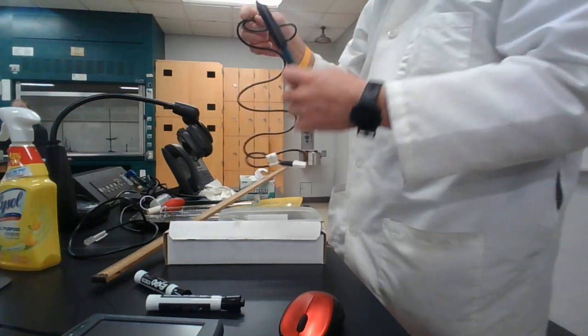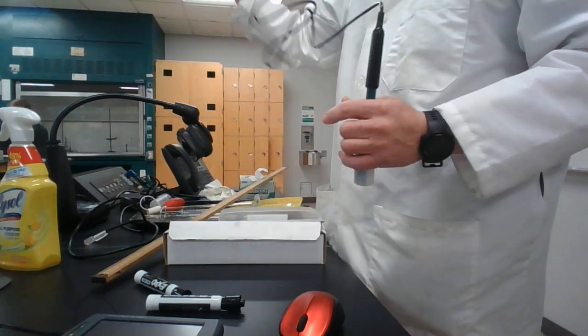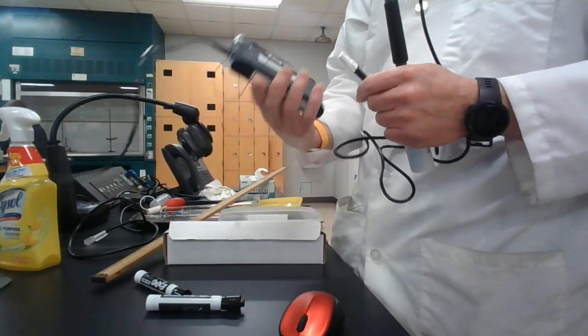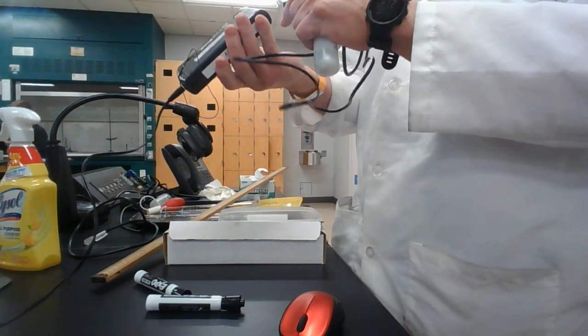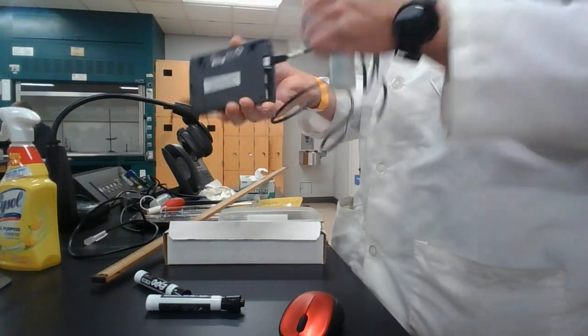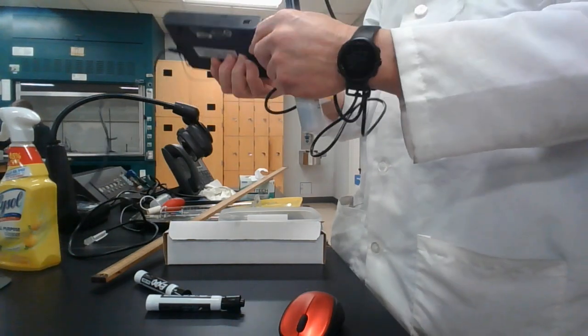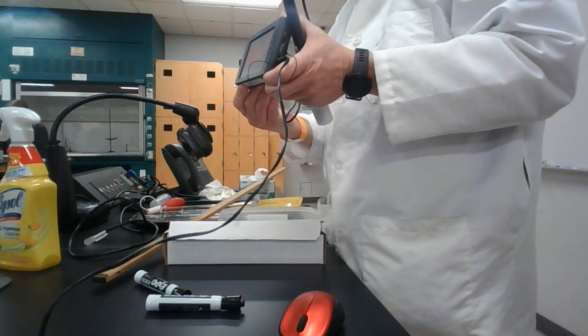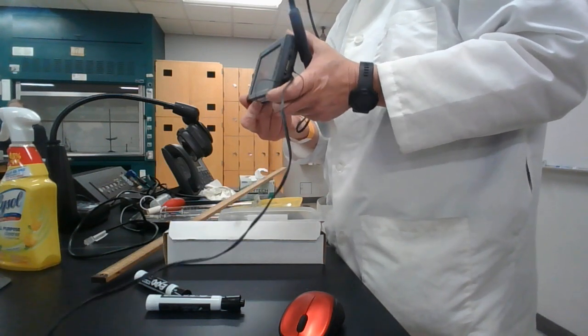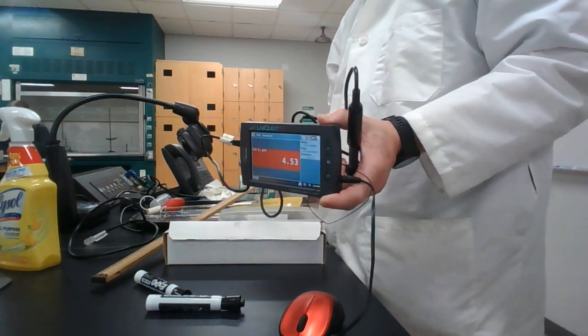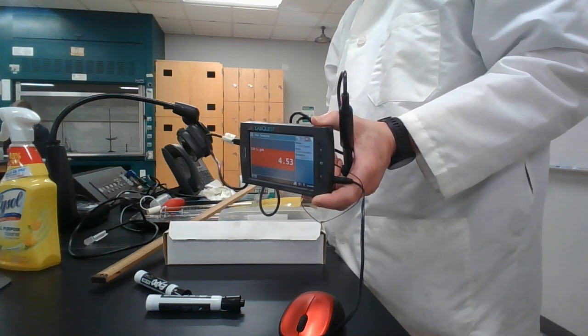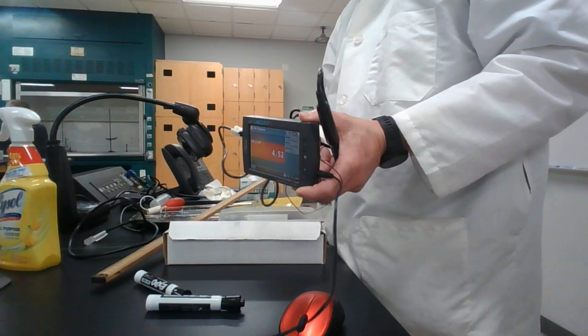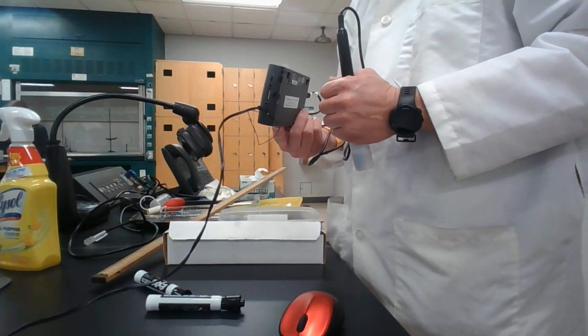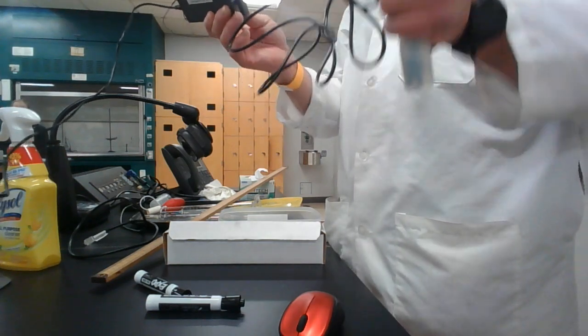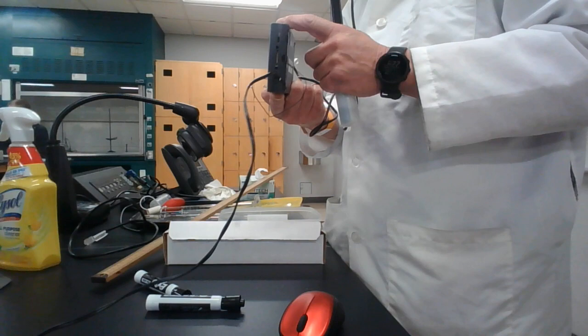And so what we're going to do is we're going to just go ahead and plug this in to the port on the side here, or channel 1. And so you use the smallest number channel. We only have one probe, so we'll just plug it into channel 1. And then it should recognize it, and you should see the pH reading of the liquid in there. No, just delete it. All right, so you're getting a real-time pH reading there, correct? Okay.